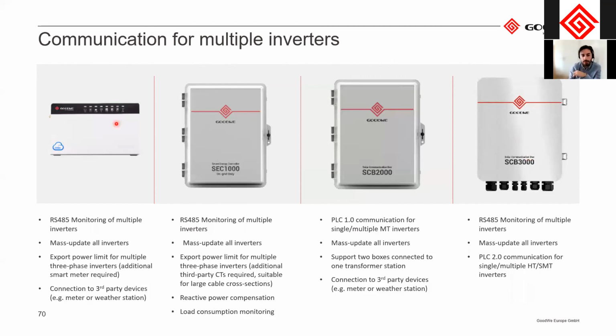Here, to communicate with multiple inverters, you usually need to connect them all to one master unit to gather all the data. And from this one, it can then control the inverters. And here we have some different boxes, but mainly the most important one, I think, is this one, which is called the EzLogger Pro. This is for residential applications and also some C&I. It is good for monitoring several inverters at once, and can be used to mass update all inverters at once. And in case you want to connect a weather station or some additional sensors, this is the unit for that.